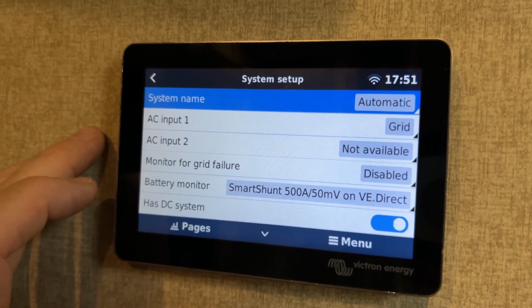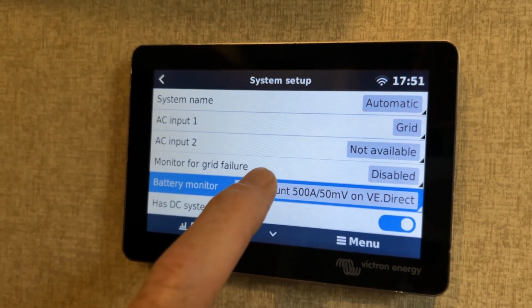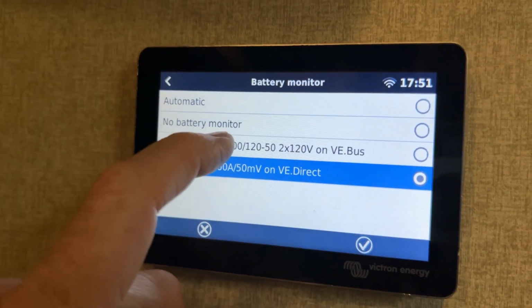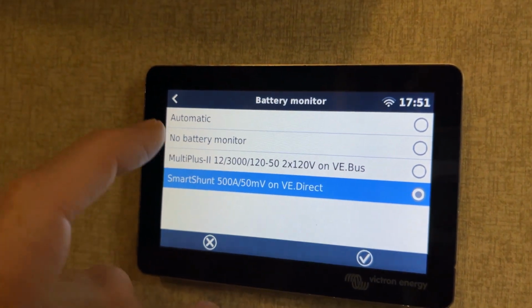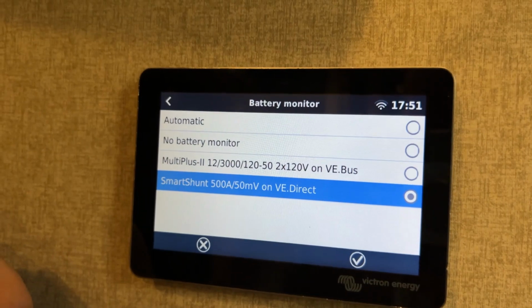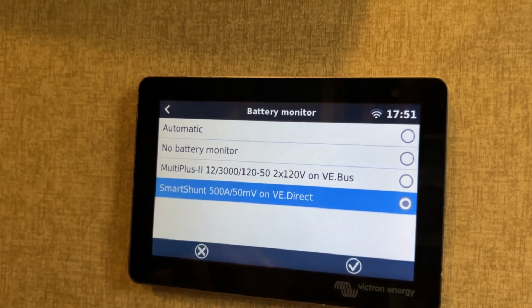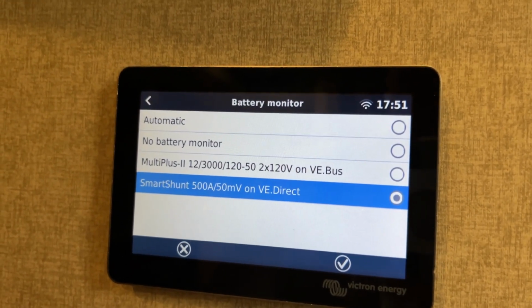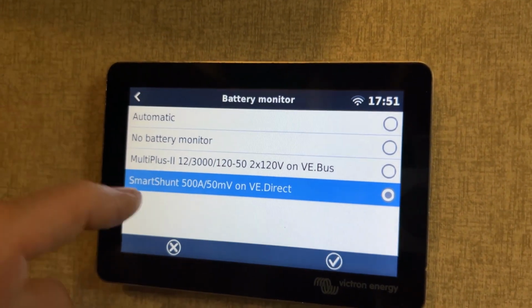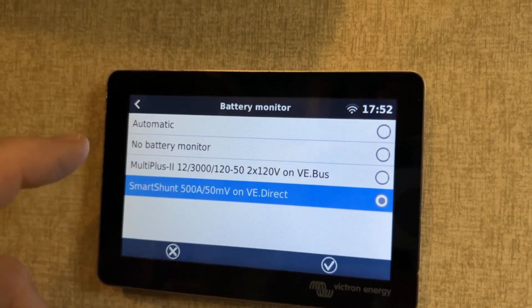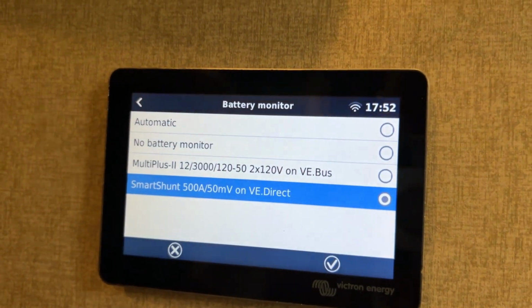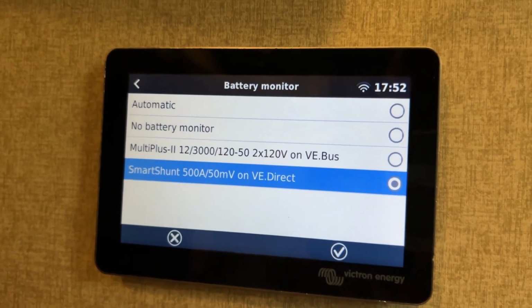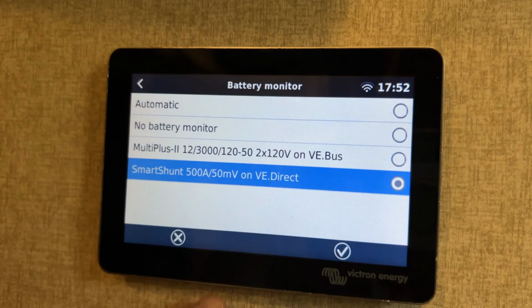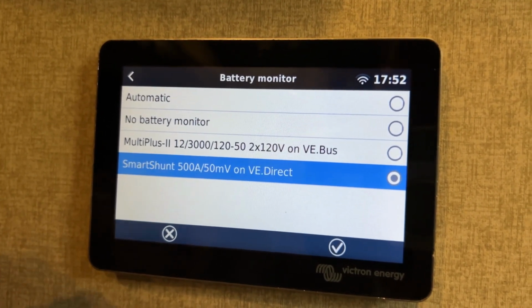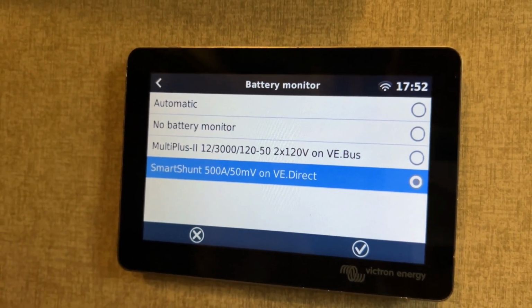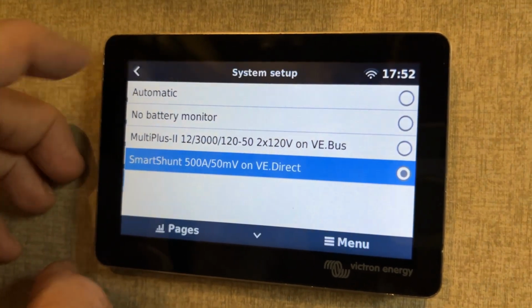For system setup, with the battery monitor I mentioned earlier, we've got the SmartShunt monitoring our battery capability. You can enable it on the MultiPlus, but if you do it there, it doesn't know the difference between your DC loads versus what it's consuming for its own inverting. It doesn't properly differentiate. So I have a shunt that monitors every watt of power going in and out of my batteries so I can monitor state of charge. That's why I use that instead of the MultiPlus—it gives a more accurate number, and it shows what my other DC loads are, separating that from the loads used by the Victron itself for inverting.